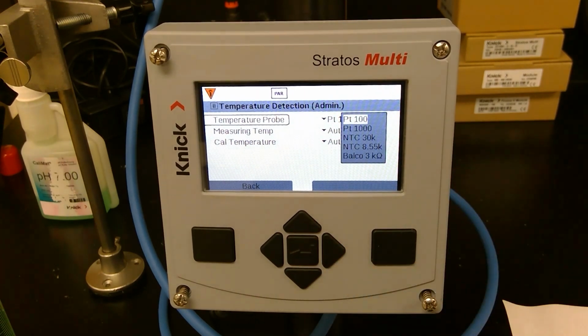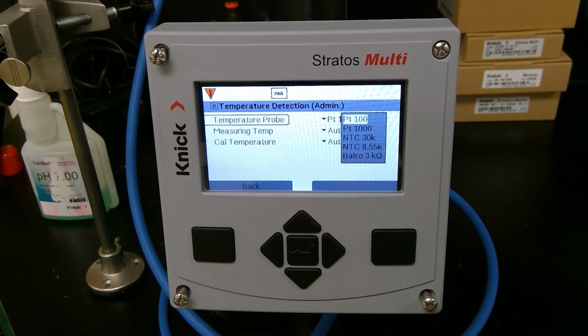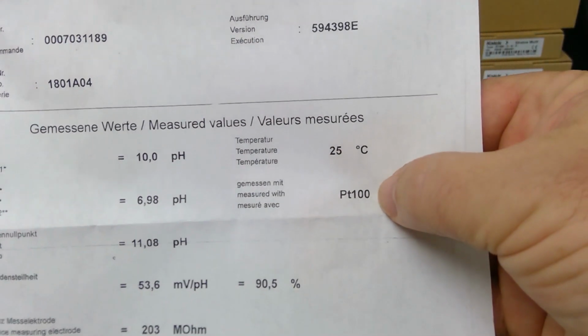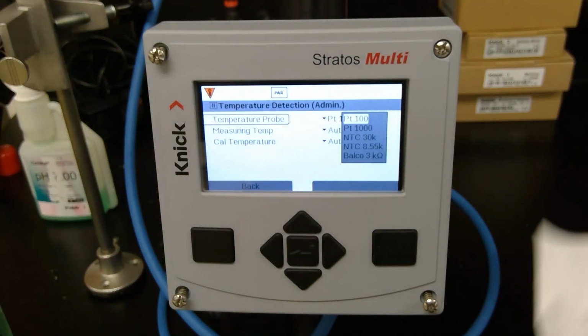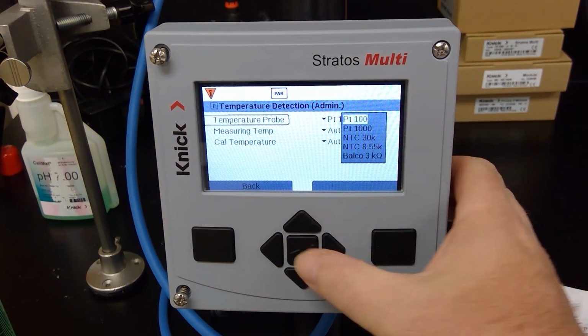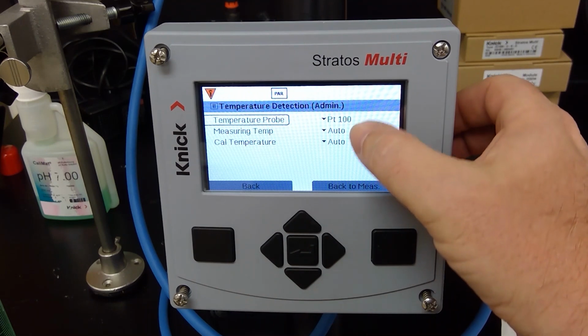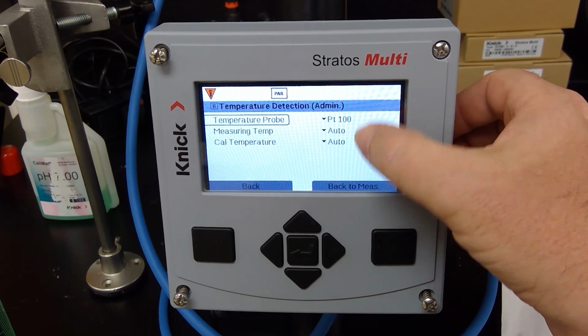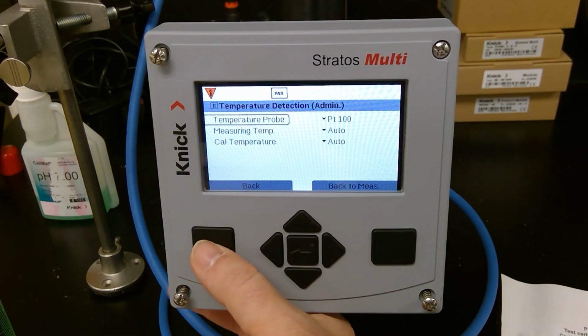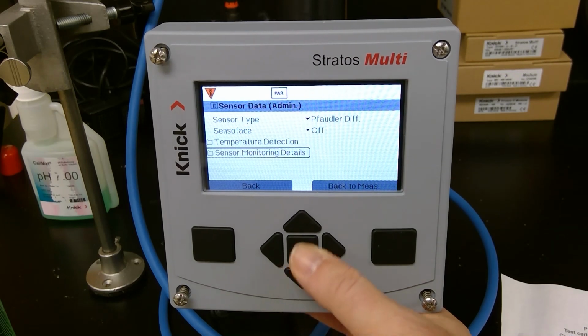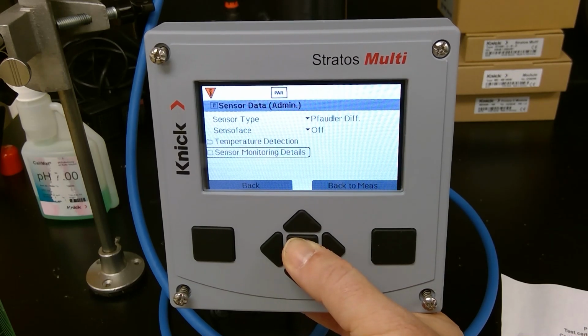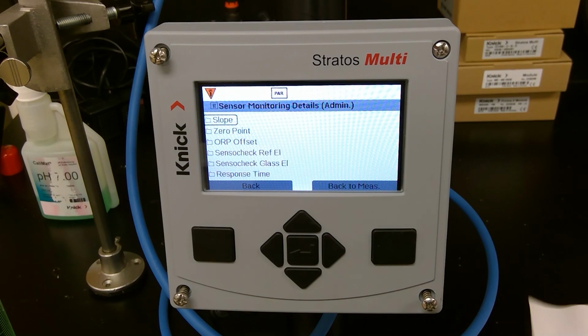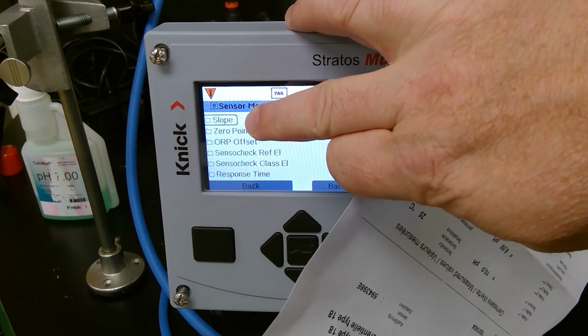We also need to identify what RTD or temperature detector is being used. And here it's a PT100, which is what we already have selected. So I hit enter, and then I leave measuring temp and cal temp to auto. So leave those auto. Then I come into sensor monitoring details. So this is very critical. We're going to adjust only the slope and 0 point here. The rest we'll leave alone.